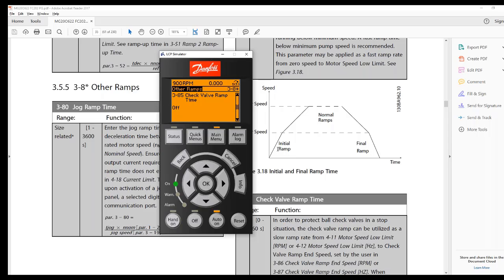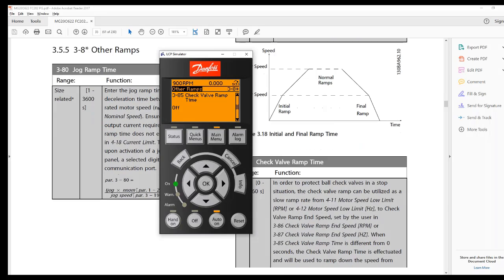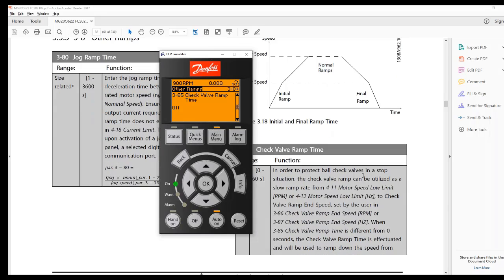And there's some other ones. And the initial ramp is here. There's one called final ramp. There's some check valve ones in here. See the programming guide for that, for bending it for a check valve, opening and closing, so you're not slamming them, flopping them open or slamming them shut. And then the final ramp time. But they're all in these three groups. So you have ramp 1, ramp 2, and other ramps.